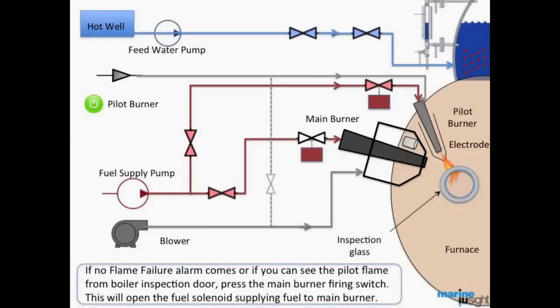If there is no flame failure alarm, you will be able to see the pilot flame from the boiler inspection door. Then press the main burner firing switch. This will open the fuel solenoid supplying fuel to the main burner.